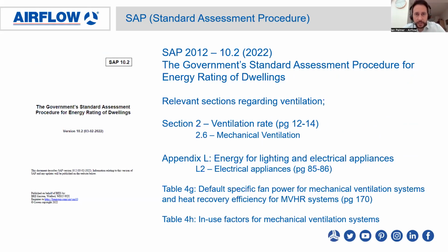Moving on to SAP, which is the Standard Assessment Procedure. This is the government standard assessment procedure for energy rating of dwellings. Relevant sections here regarding ventilation is section 2, where it covers the ventilation rate, mechanical ventilation, and then Appendix L, which is energy for lighting and electrical appliances, and L2, which is specifically electrical appliances. Table 4G talks about the specific fan power for mechanical ventilation systems, and heat recovery efficiency for MVHR, and Table 4H use factors for mechanical ventilation systems.